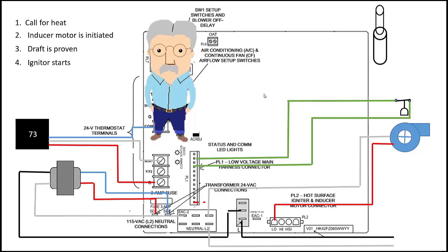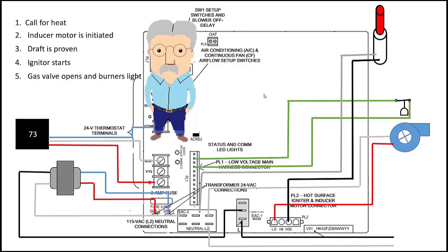And that is our igniter is going to start. So let's put an igniter in up here. This is a hot surface igniter and we'll wire it up as well. When the next step starts, it's going to glow bright red. Once the circuit board knows that it's hot, it's going to open the gas valve and the burners are going to light.